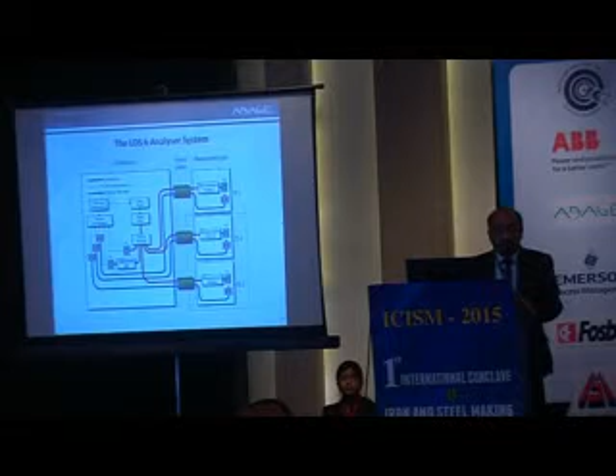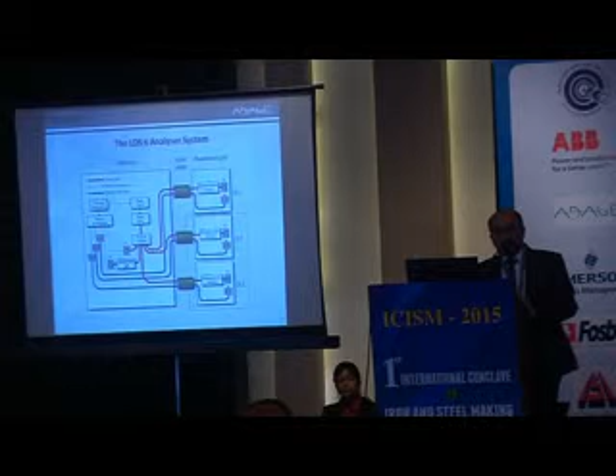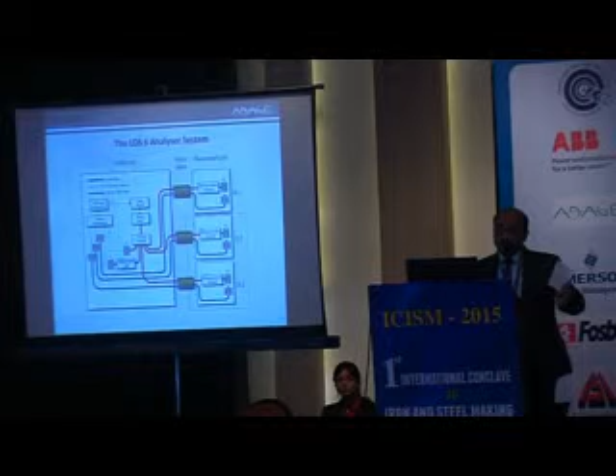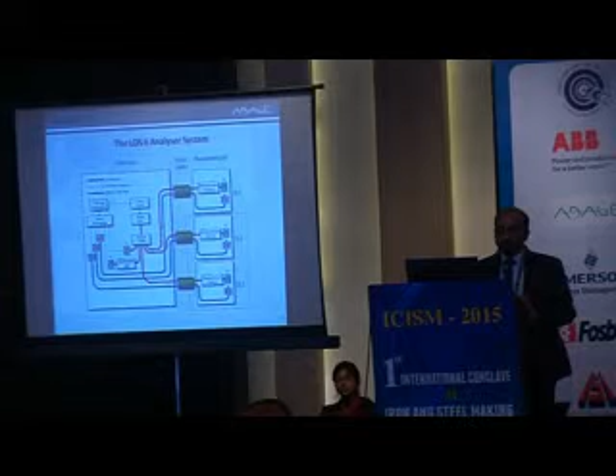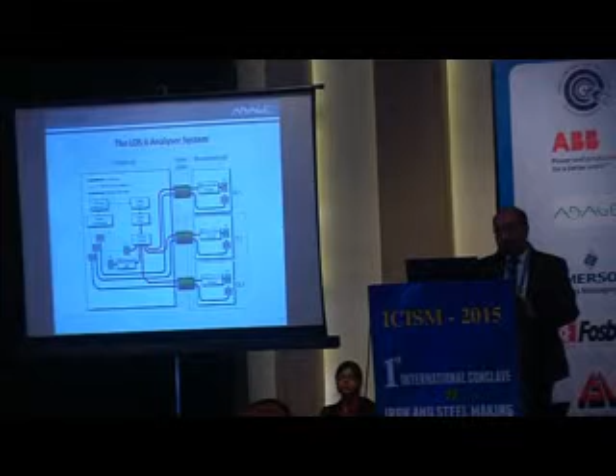We don't just certify it ourselves - it's certified by certifying agencies, and that gives immense benefit in terms of maintenance and in terms of consumables like calibration cylinders and bottles. The stability of calibration, and of the cylinders, is always a question - plants located in very remote places face huge issues with availability of those cylinders. Gone are those days - you don't need them. It's a lifetime calibration-free instrument for the life of the analyzer, and that's true. This is one of the advantages.